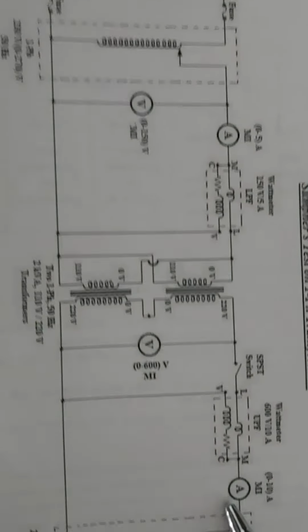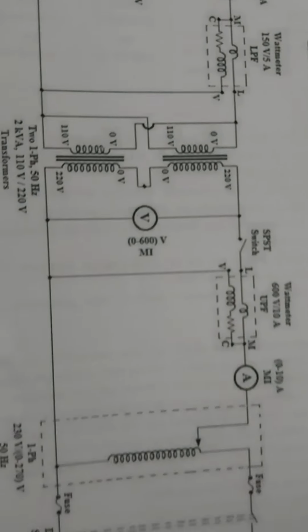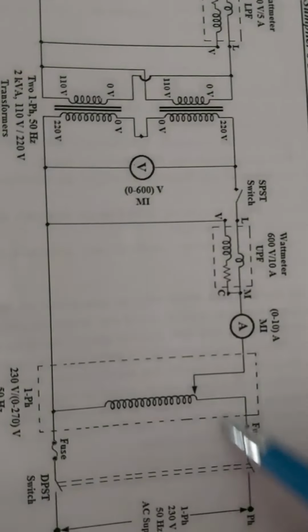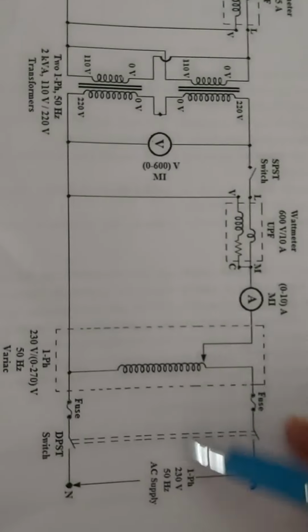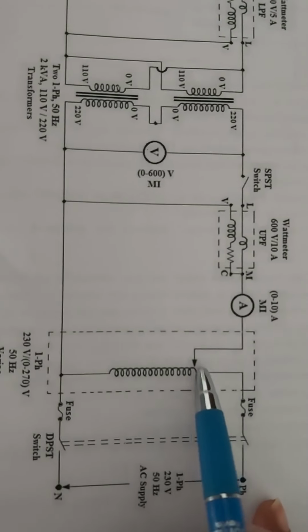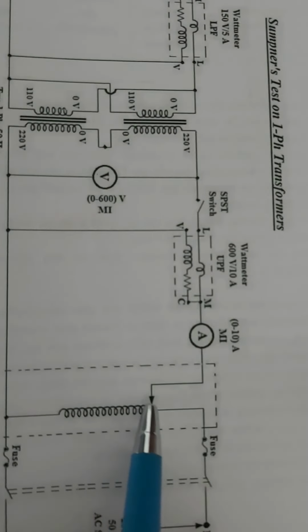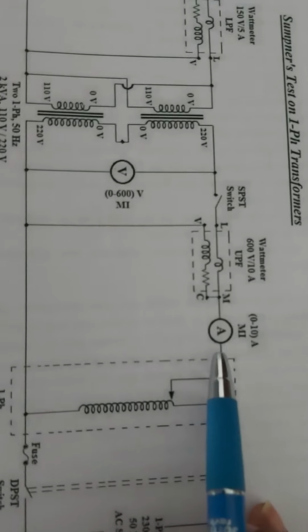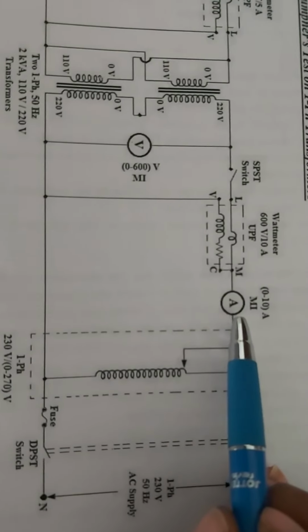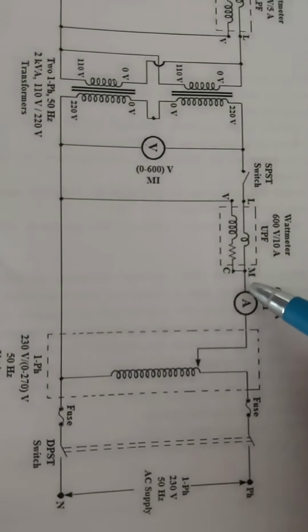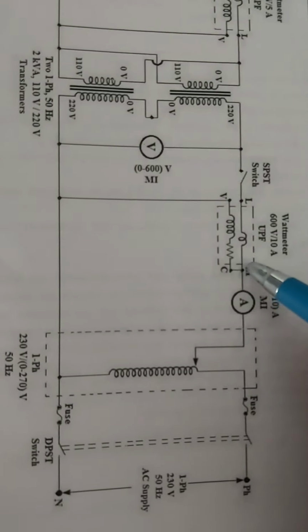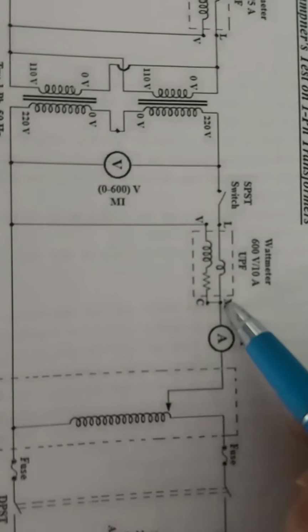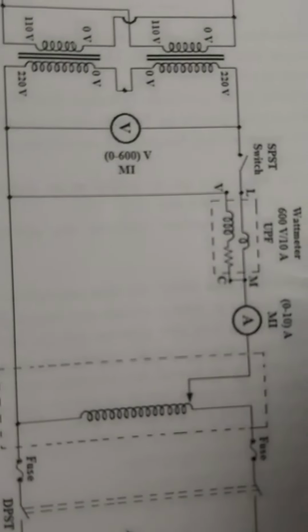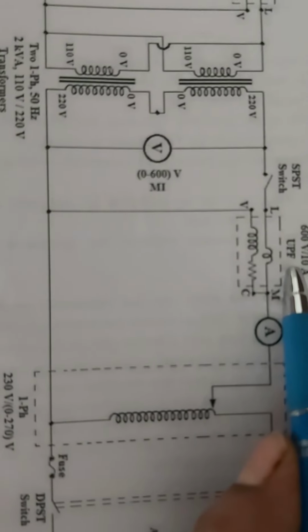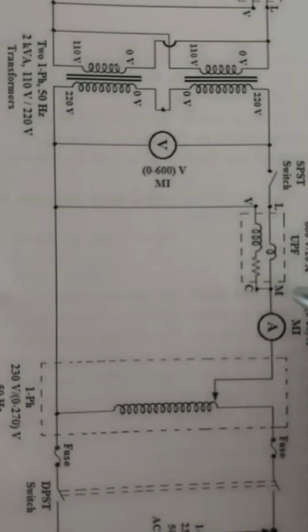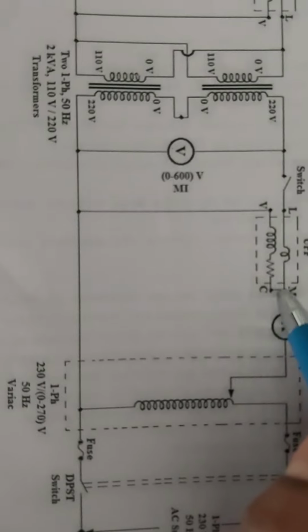Coming to the secondary side, you have to start the connections from the variac side, from right to left. From the variac I take one wire, which is connected to the positive terminal of the ammeter, and the second terminal of the ammeter is connected to the M terminal of the wattmeter. Here on the secondary side we are using a UPF wattmeter, and MC will get shorted.